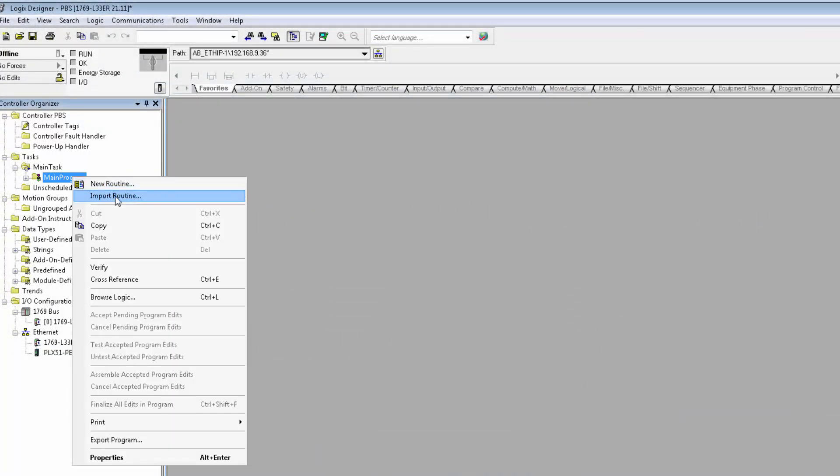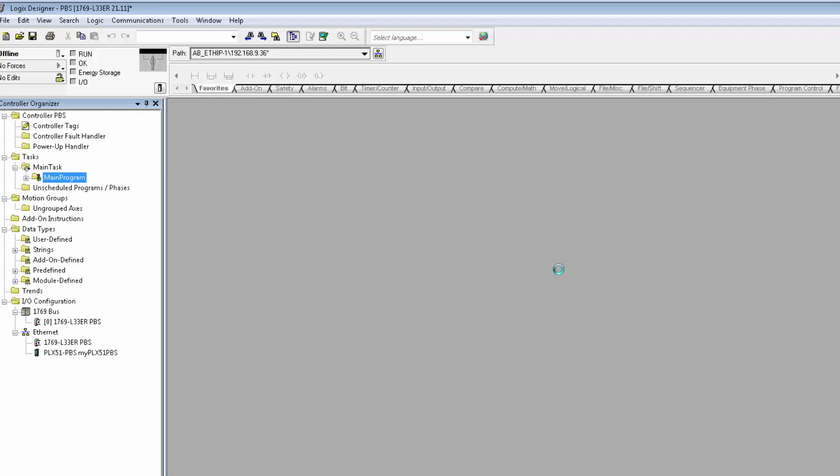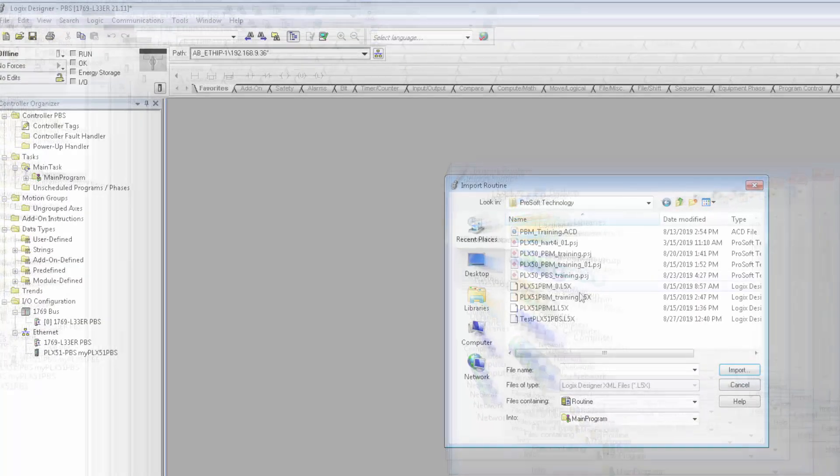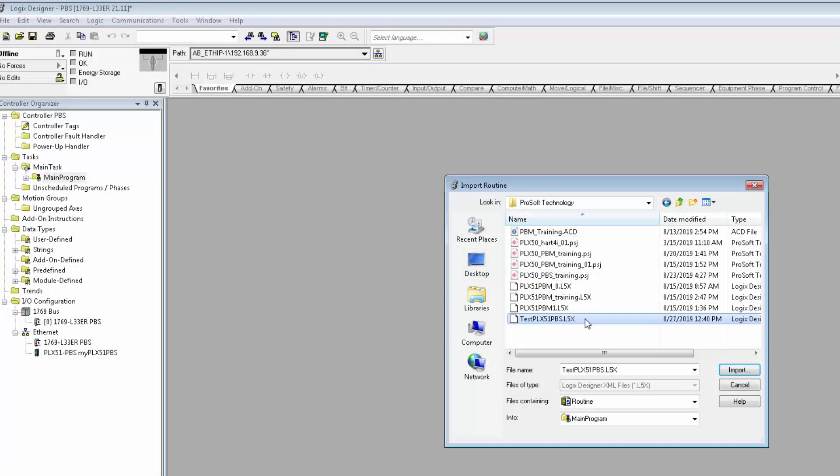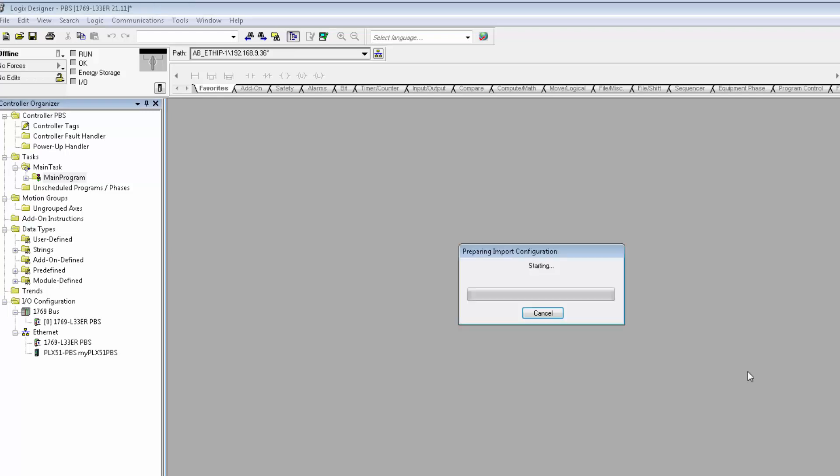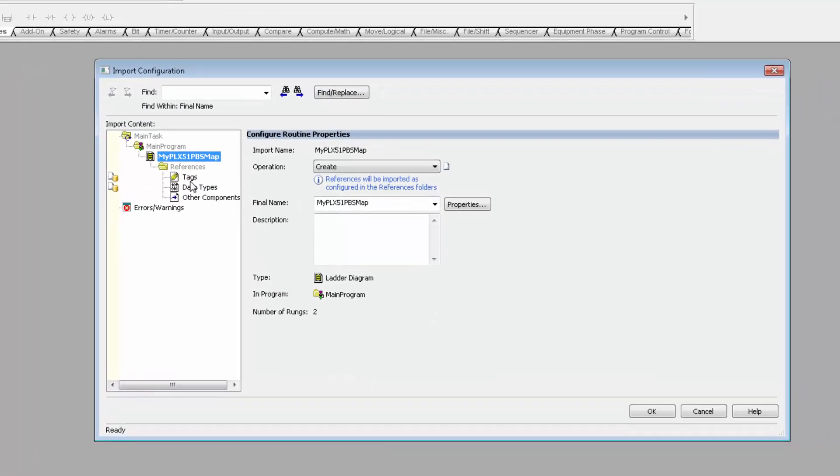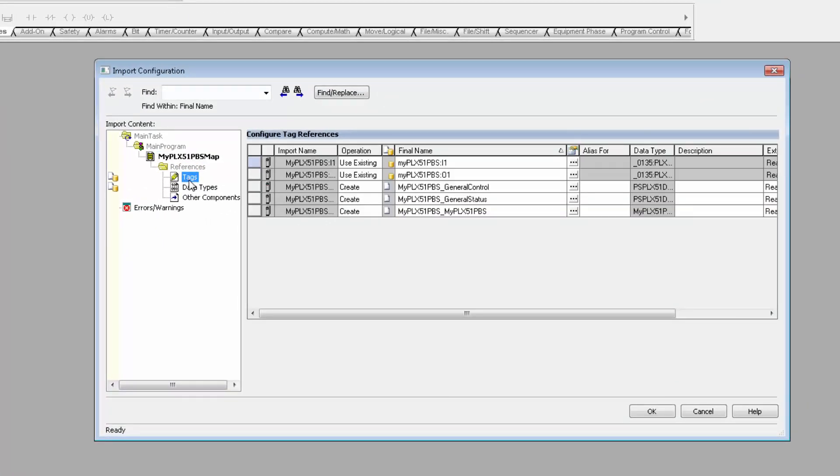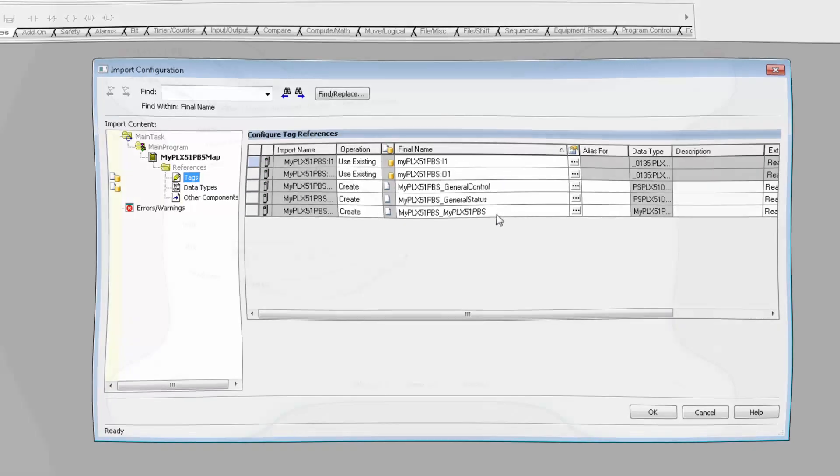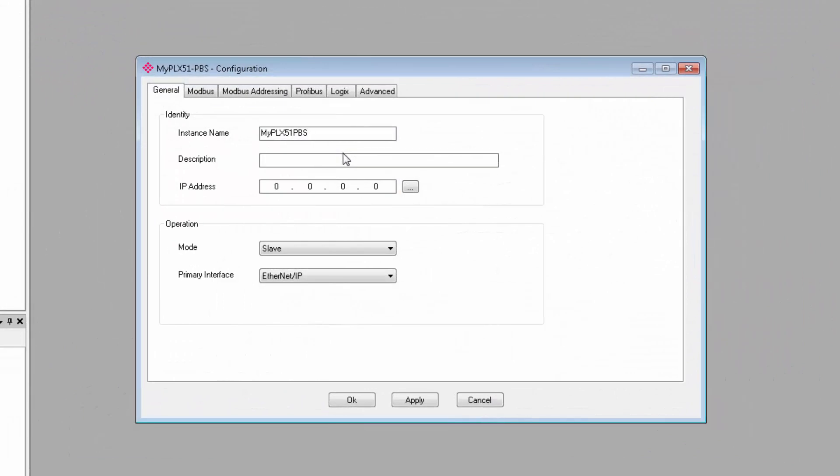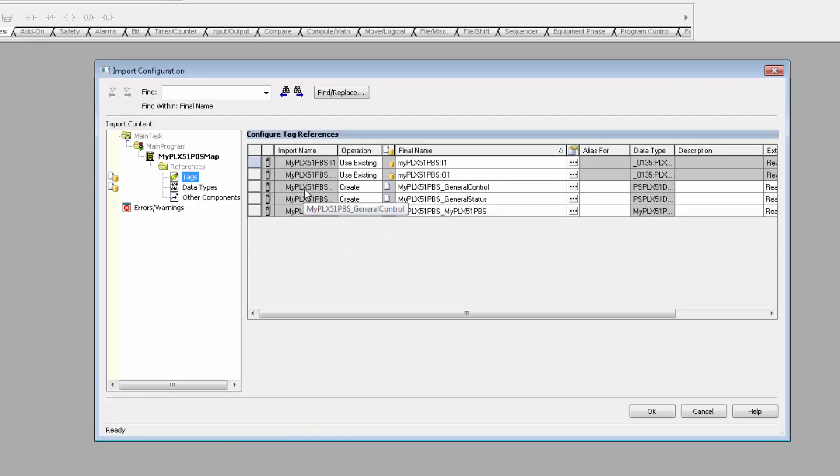Under Main Task, go to Main Program, right-click and choose Import Routine. Choose the L5X file that we exported and click Import. In the Import window, you can see the tags that the routine is bringing in. Note that the name for the Input and Output under Final Name needs to match the name that we gave the PLX51 PBS under the General tab back in the Configuration Utility. Now I just gave it the name that I knew would be generated here. Otherwise, you can edit the names here to match what you entered in the Configuration Utility. Just know that if it doesn't match, you'll see an error here.